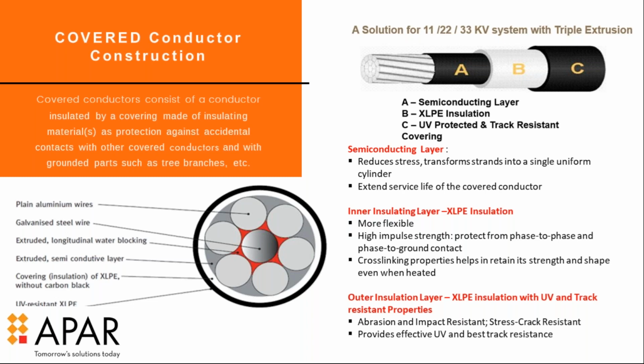The covered conductor construction is very simple. For example, we have taken an ACSR conductor, where the middle strand is steel, and over it are aluminum wires, the aluminum conductors. The red portion you see is filled with a kind of semiconducting gel, which prevents water or moisture from ingressing. So it is a totally water-blocked conductor, which we have to make for the covered conductor purpose.